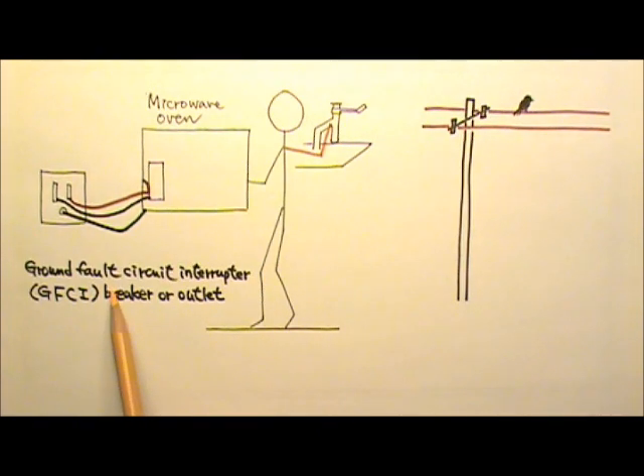A ground fault circuit interrupter, GFCI breaker or outlet can detect current leakage of 5 mA or more, and shut down the electricity to limit damage caused by such leakage.